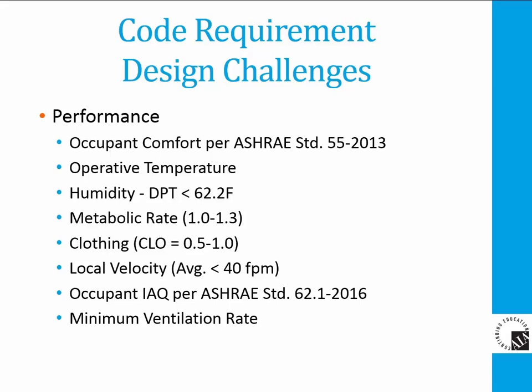ASHRAE Standard 62.1 prescribes the minimum ventilation requirements for the space. CFM requirements vary depending on the space usage based on Table 6.1, with a combination of CFM per square foot added to the CFM per person requirement. These baseline CFM requirements are then adjusted based on the system used.